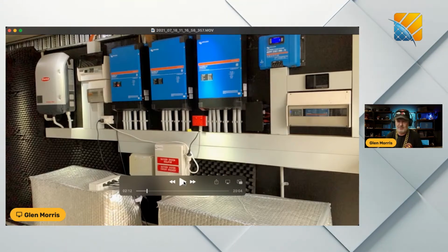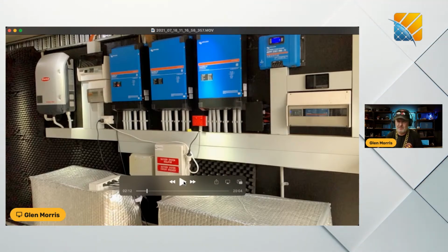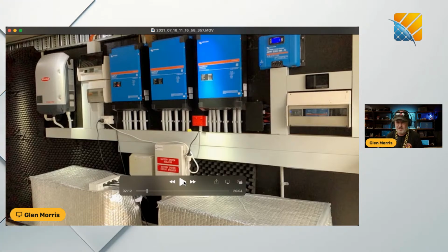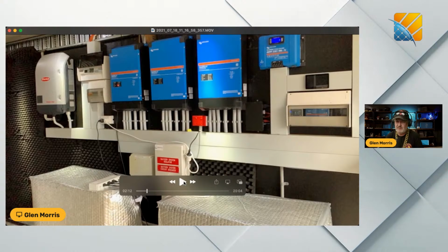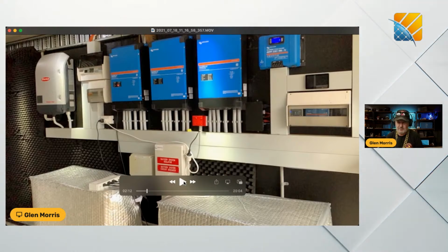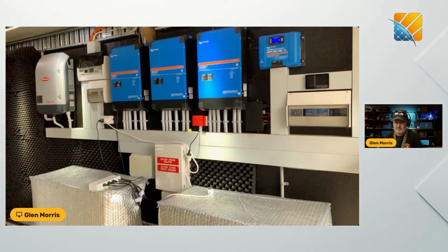So what you're looking at here is 3 5 kilowatt Multi-Plus 2s, 1 per phase, and they have a synchronization cable that goes between them so that the master on the left controls the phase angle of the other 2 and therefore creates true 3-phase. Below it in those lovely silver boxes is a couple of Redflow batteries.